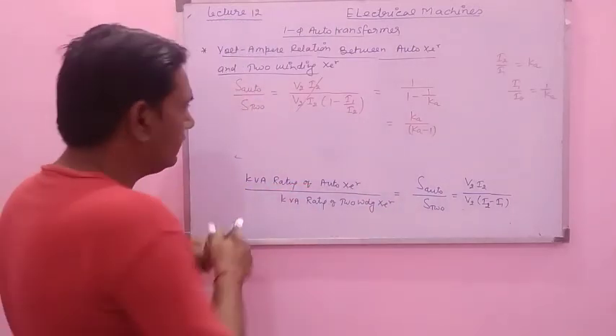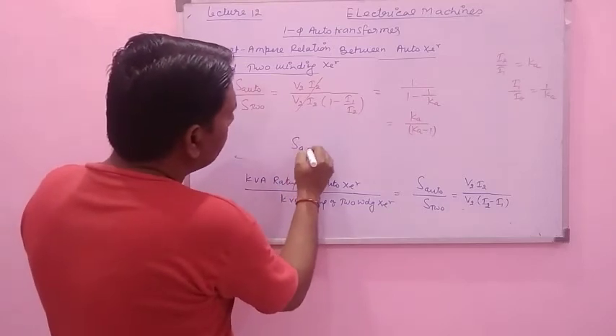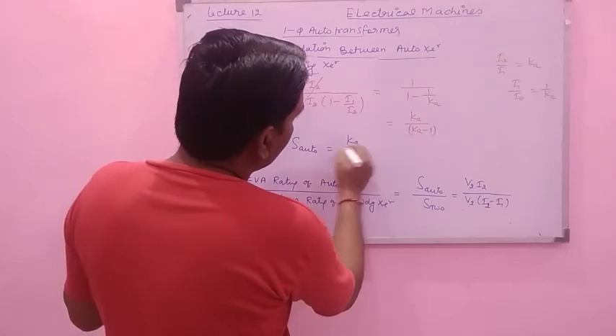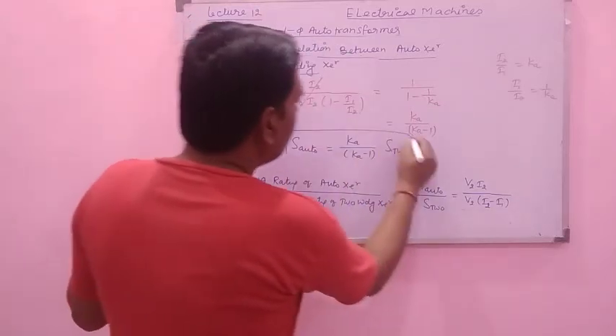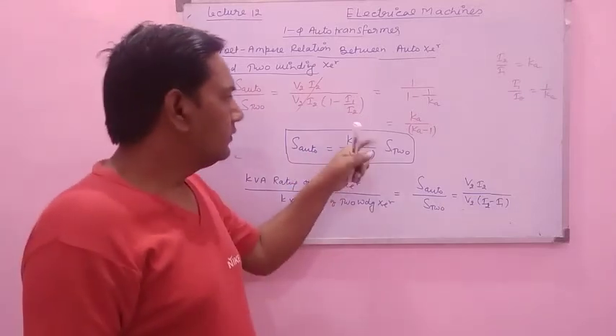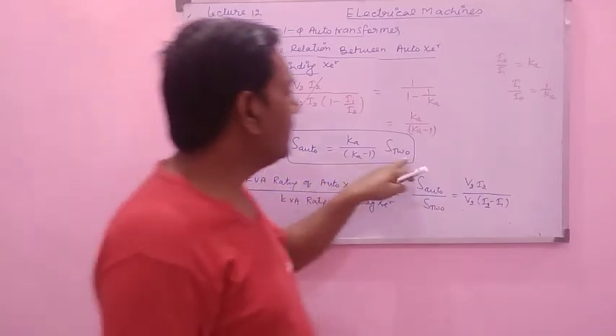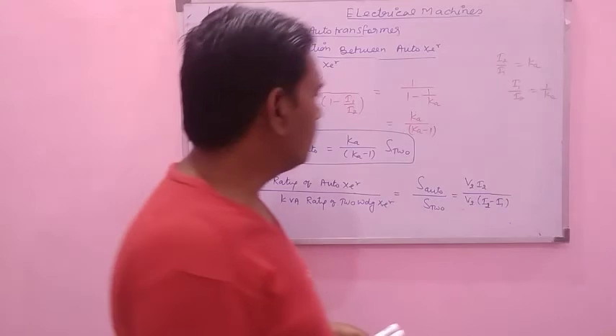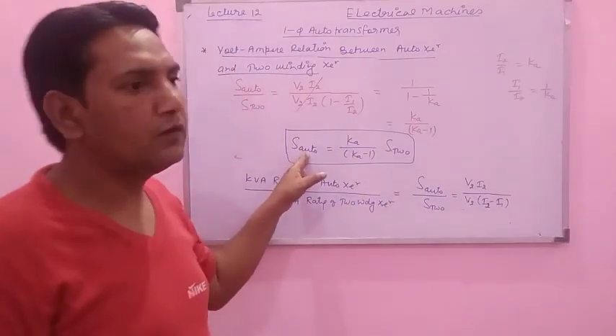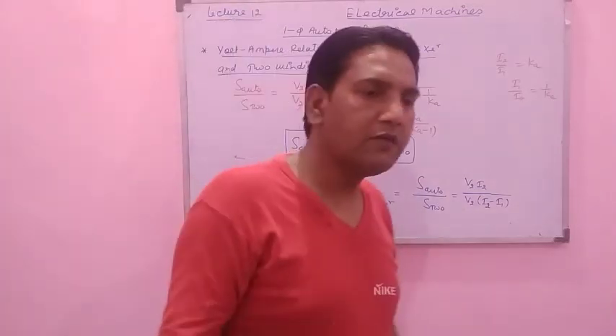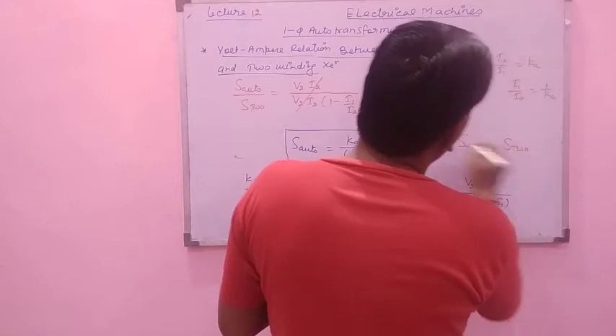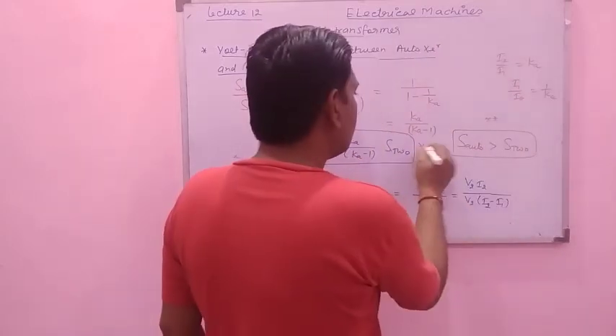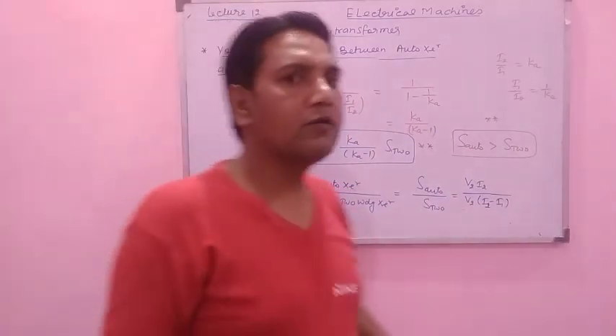So the rating of auto transformer S auto is equal to Ka upon Ka minus 1 into the rating of two winding transformer. You can see that the rating of auto transformer has increased compared to the rating of two winding transformer. If a two winding transformer is of 20 kVA, the rating of the auto transformer will be greater, it may be 50 kVA or 60 kVA. So S auto is greater than S two winding transformer. Keep this important point in mind. This is the volt-ampere relation between the auto transformer and two winding transformer, a very important topic.